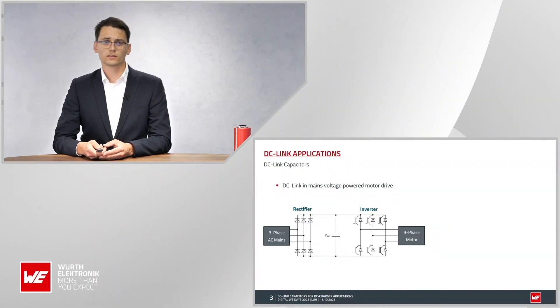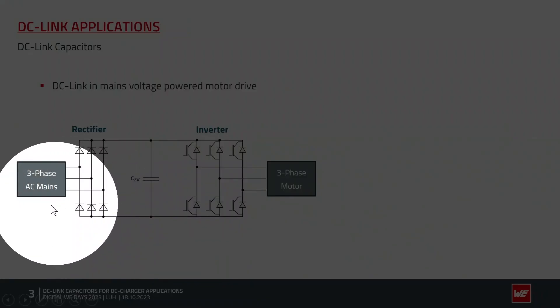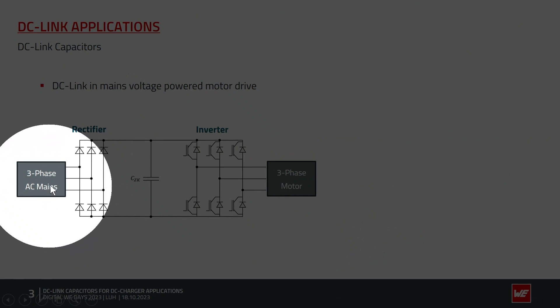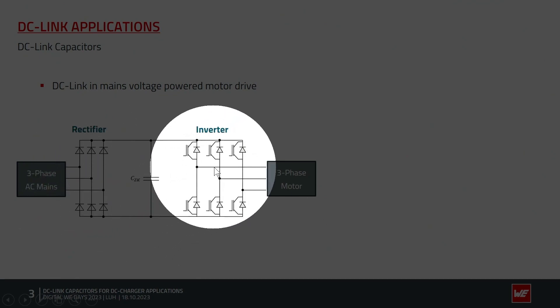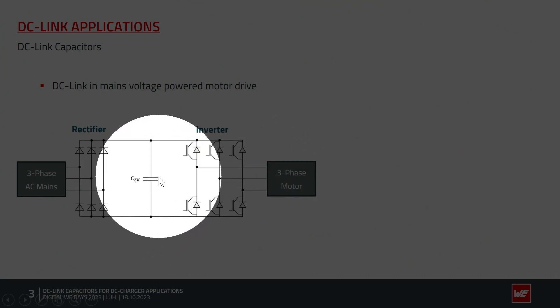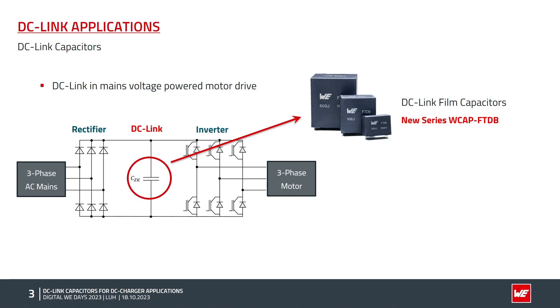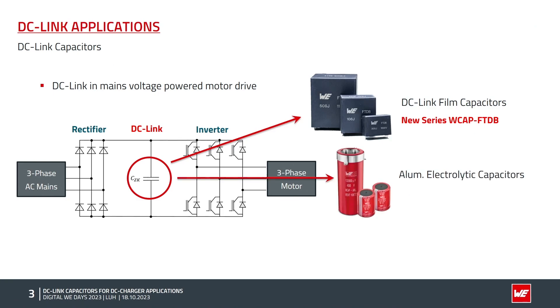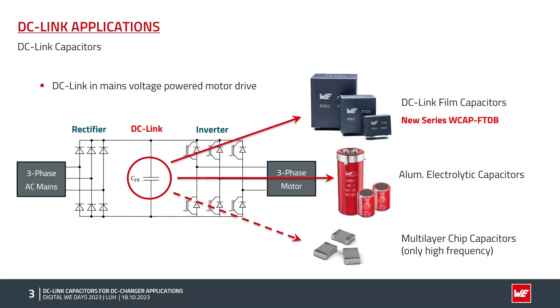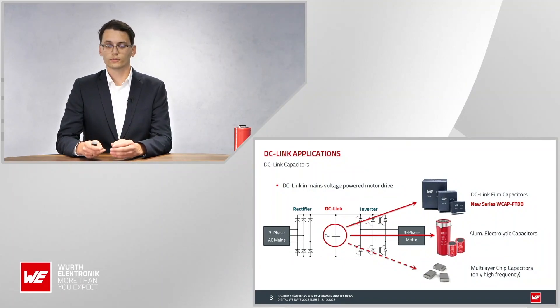Let's start with the DC-Link application in general. From the left-hand side you have the three-phase AC mains, then a rectifier, then an inverter, and on the other side the three-phase motor — with the DC-Link capacitor in between. The question is which technology to use for this capacitor: DC-Link film capacitors, aluminum electrolytic capacitors, or for some applications MLCC, which are more interesting for higher frequencies because smaller capacitance values can be used.